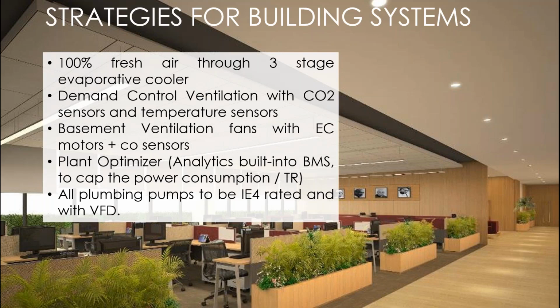And one very important thing, plant optimizer. Now, we all know buildings have got BMS, but BMS have simply been reduced to being a plant operator. Turn the chiller on, turn the chiller off, turn the pump on, pump off, scheduling, cycling. But what a plant optimizer does is put a cap on the energy consumption. So for example, if I feed into the software, please limit my power consumption of the central plant to 0.7 kilowatt per ton, including chillers, pumps, cooling towers, it would make sure that everything is working in combination. So for example, whether to run one chiller at full load or two chillers at 50% load, it will see the graph, the curves of all the equipment, which we also feed into the simulation software, and make sure that the optimal combination of plant is working. Next slide, please.